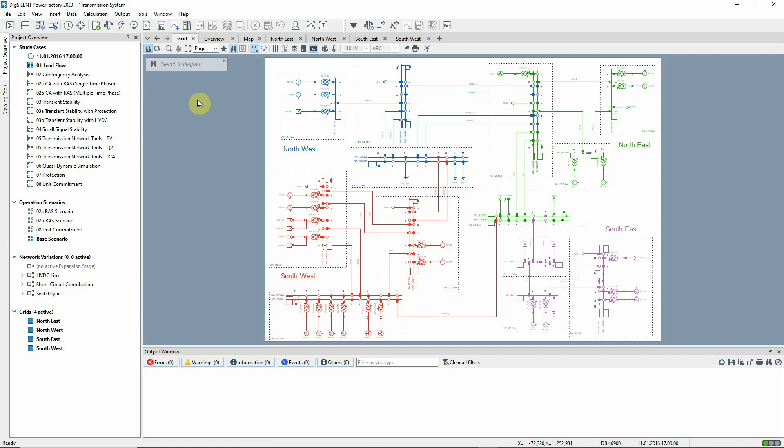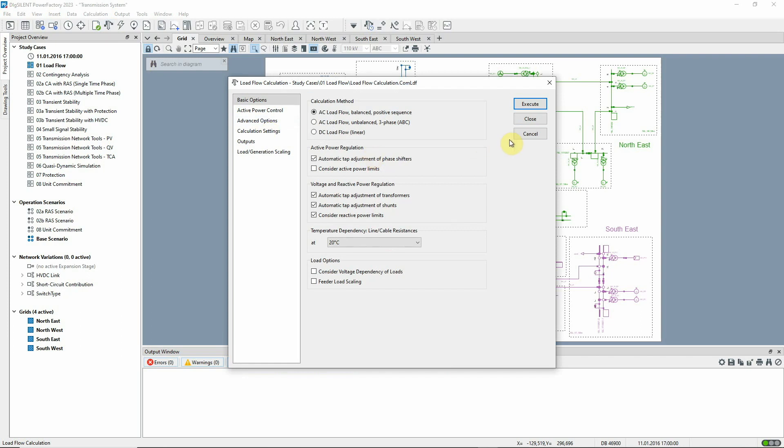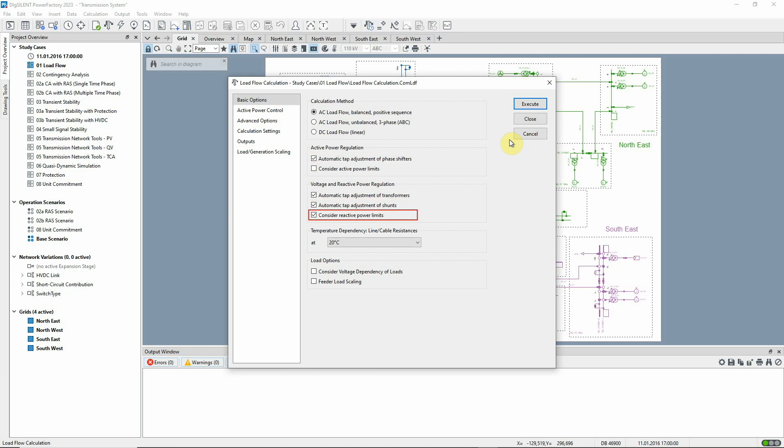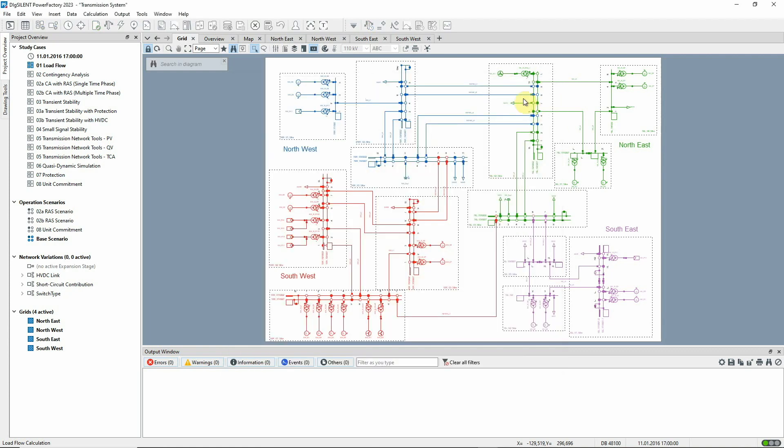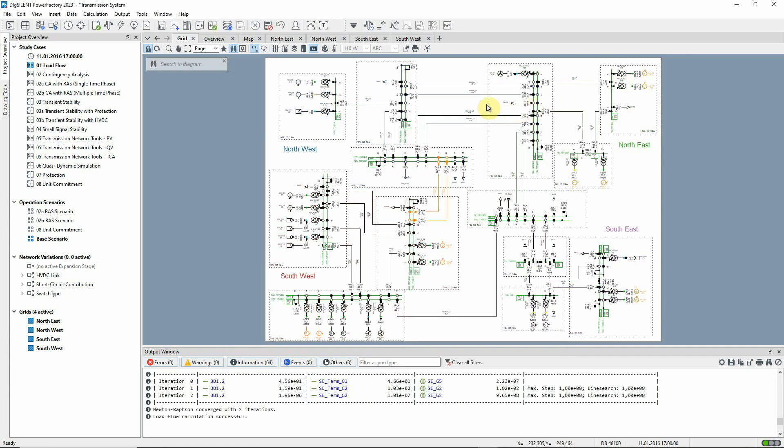The load flow can be run using this icon on the main toolbar. Let us look first at the basic options. An AC load flow will be run with automatic adjustment of taps for phase shifters, transformers and shunts, and the reactive power limits of generators and SVS's will be observed. On the active power control page, the active power control is as dispatched with any mismatch between generation and demand being taken up by the reference machine. Click on Execute to run the load flow.